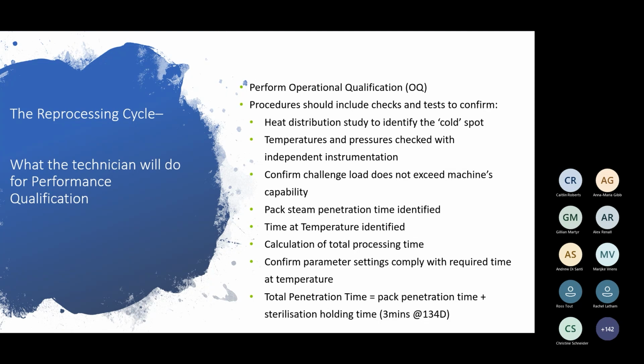Pack steam penetration time identified. So when they put the probes in the machine, they're going to put one probe inside your challenge pack, and they're going to make sure that the temperature is reached inside the pack at the same time as the outside of the load, or if it takes longer to reach steam penetration within your challenge pack, then they'll adjust the whole sterilization holding time to make sure that the 3 minutes is still met within that challenge pack. It may extend your time on the whole processing of the sterilization cycle. Time at temperature is identified, and that's 134 degrees at 3 minutes. So they identify and make sure that that is being met.